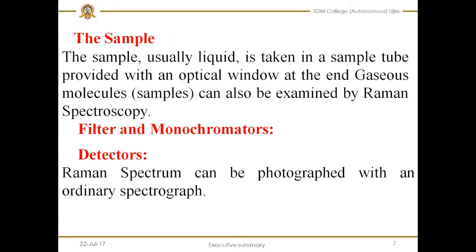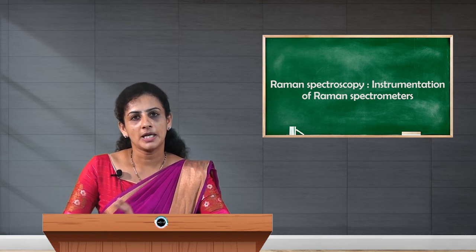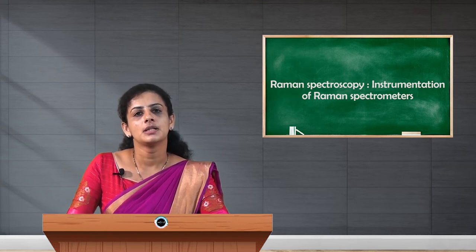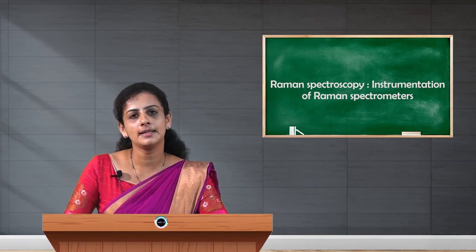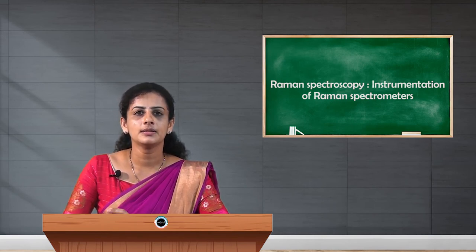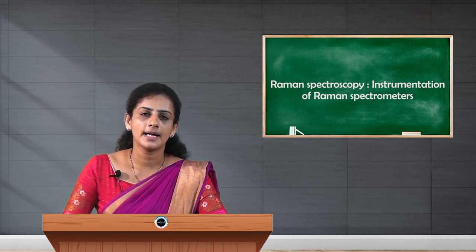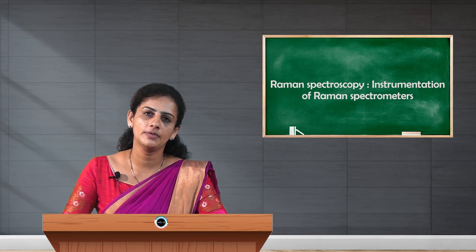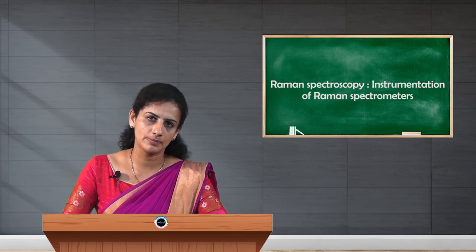The next component is the sample. The liquid sample can be taken in a sample tube, and that sample tube is provided with an optical window at the other end. Gaseous samples are also measured using a Raman spectrometer. If the mercury arc lamp is used as a source, then the radiation passes through the cylindrical walls of the sample tube, then the light is scattered and the scattered light escapes out of the optical window present at the other end of the sample tube.